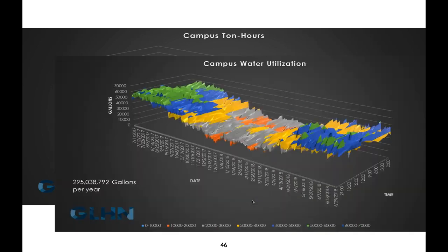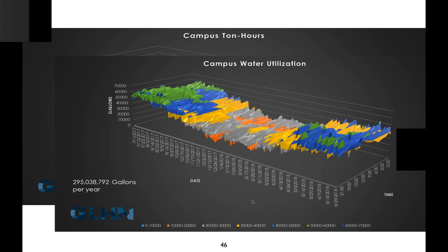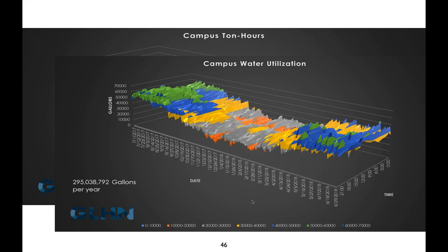And that correlates almost directly into this campus water utilization. Every ton hour here represents 2 gallons of water. So that's a fairly simple calculation, there's some simplification here. It's a little more complicated than this, but fundamentally that's how we get to, of the university's 550 million gallons a year, the cooling towers are consuming almost 300 million of it.